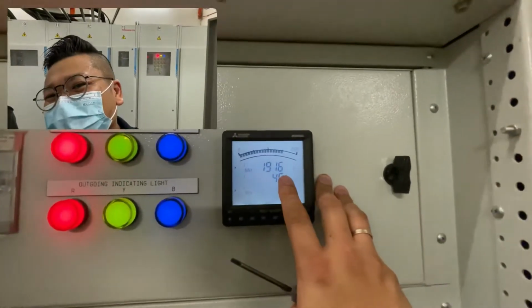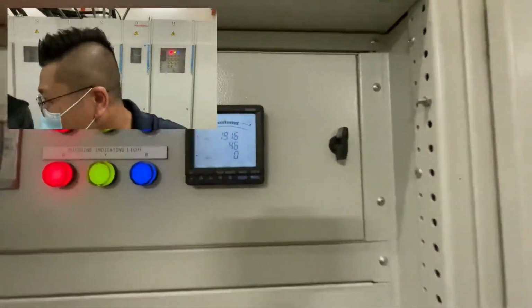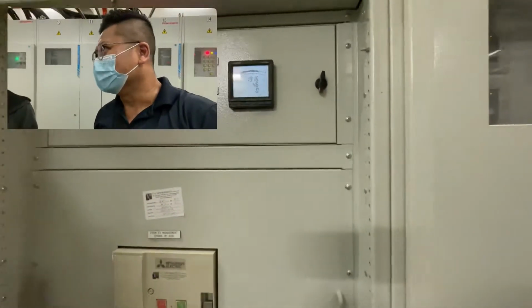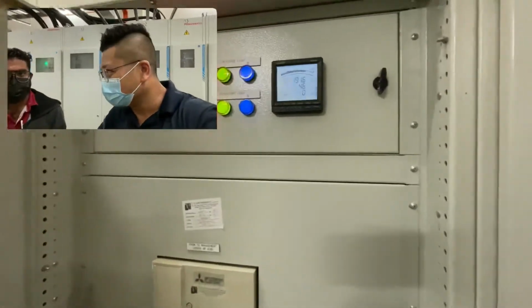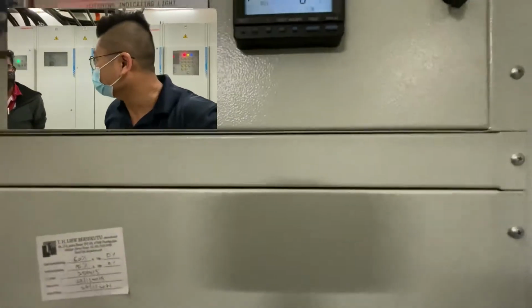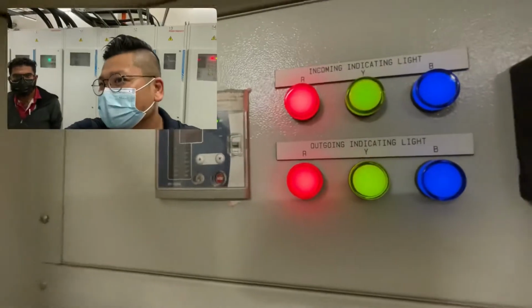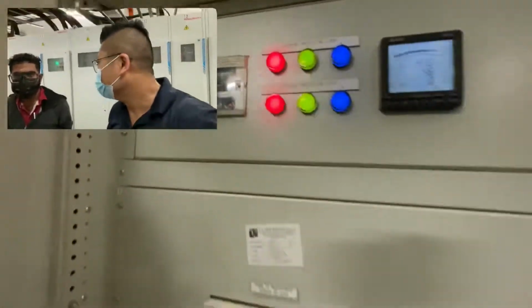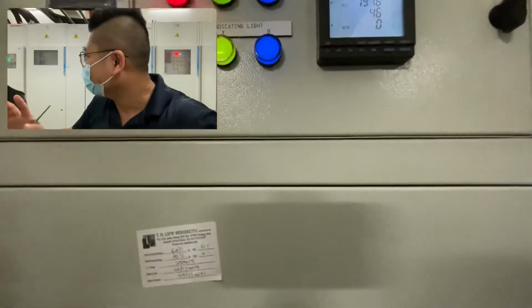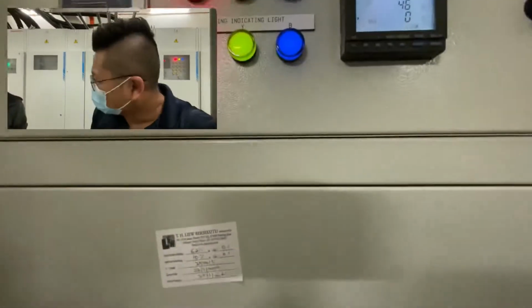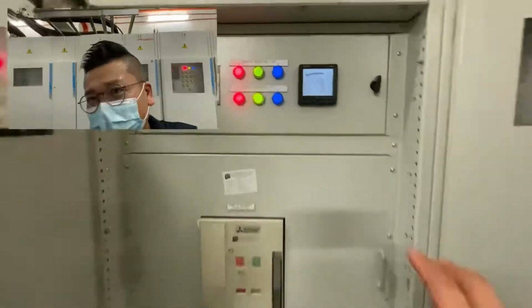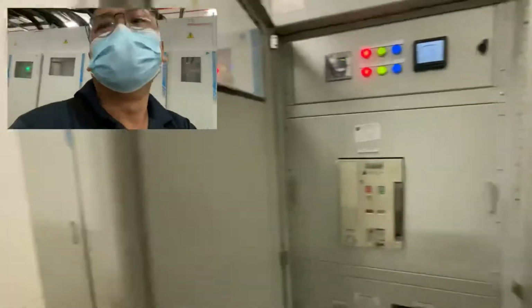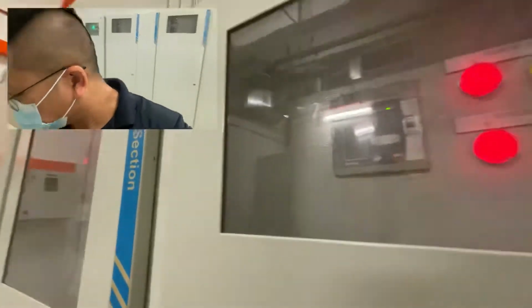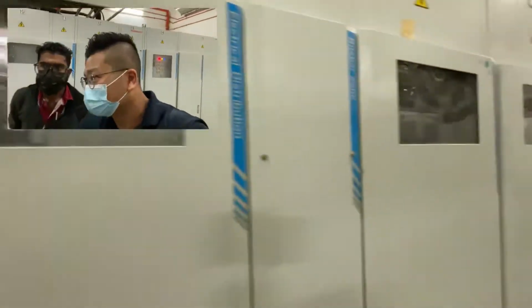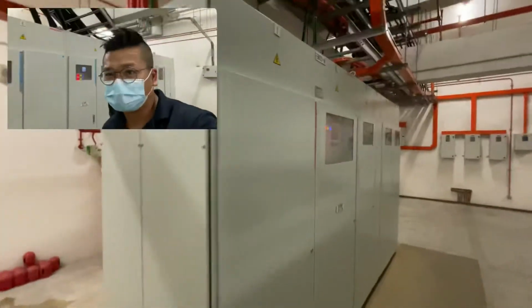The 1916M is recorded during previous time. Previous time, that means I don't know how many months already, during when they test everything, during the commissioning time. That's why everything run, it is recorded 1916. When they run all the firefighting equipment, all the fan, I think most probably is during the bomba testing. It's recorded this on the high side. We are not able to test the genset, otherwise I'm going to show you how to jump the signal from here. Oh, okay.